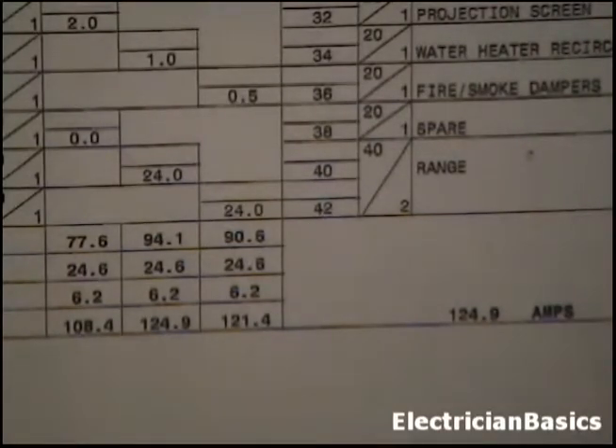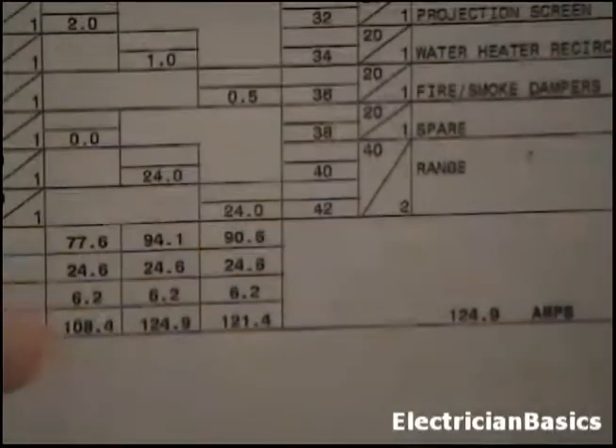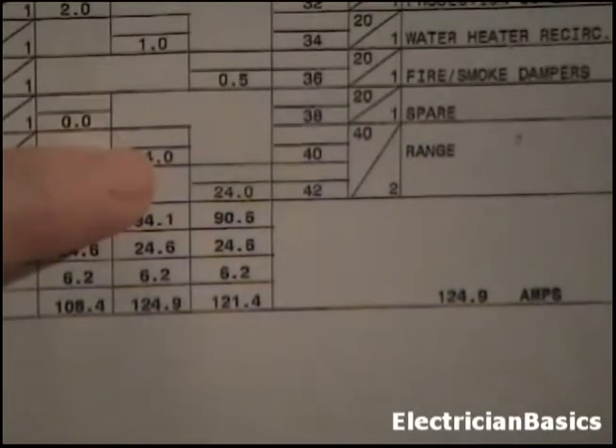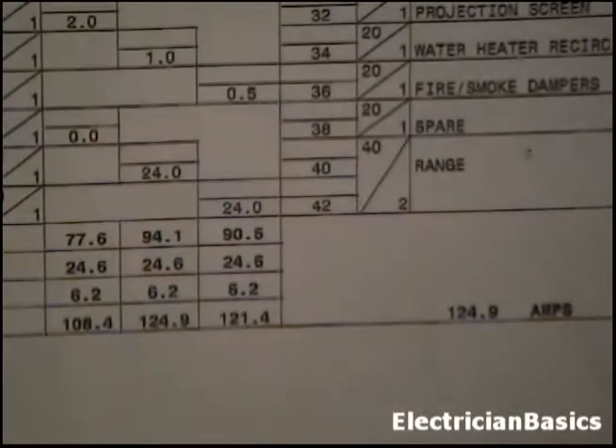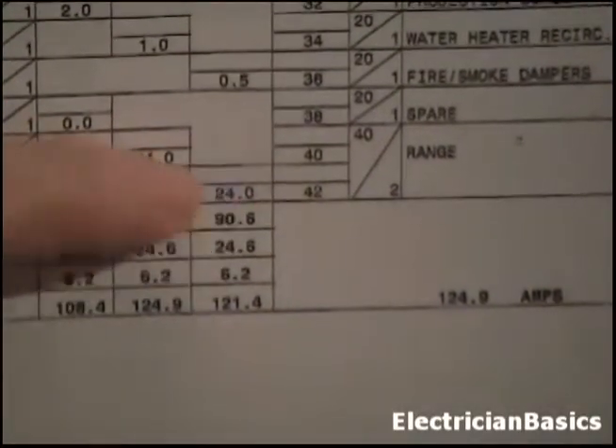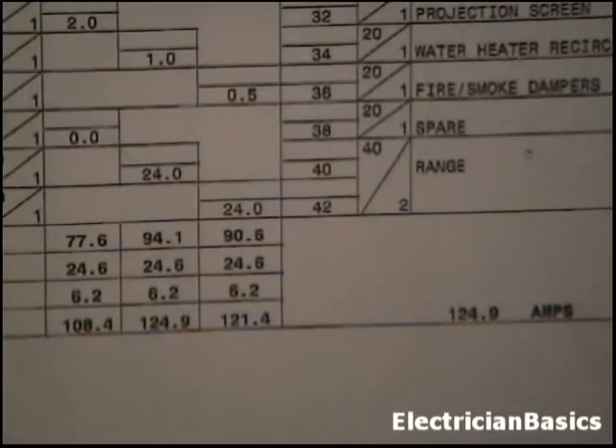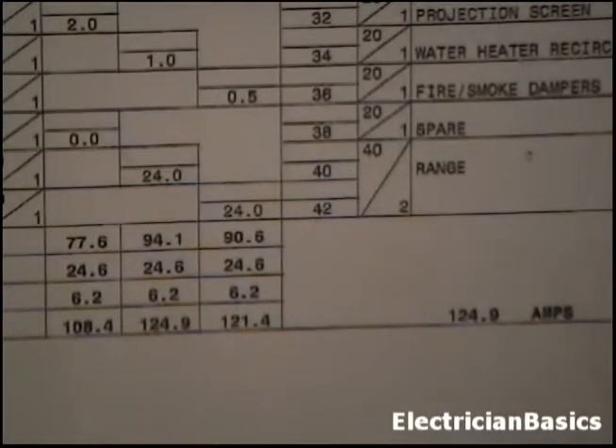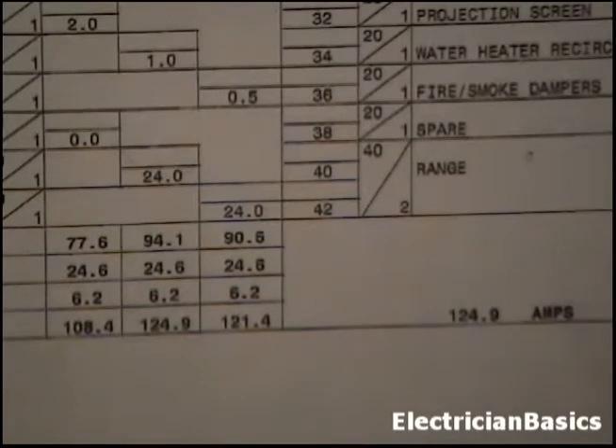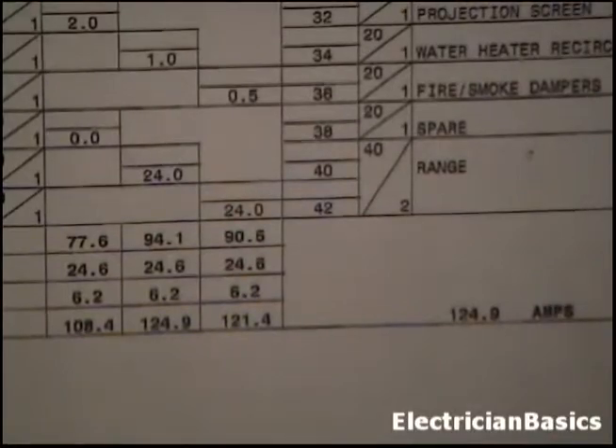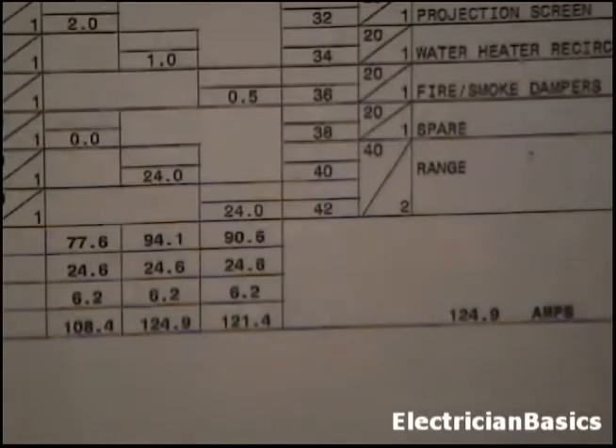The phases, we asked what phases those were, and if you read over you can see that it's 24 amps and 24, and it's on B and C. Now you would expect, once again, these to be the same number, because from each phase you want the same amount of current going in to whatever that 2-pole breaker is controlling. Hopefully you looked at it and you came to the conclusion there's only one 2-pole breaker, and hopefully you also remembered that we went over this when we were talking about the plugs in the break room and how we had to locate those within the millwork.